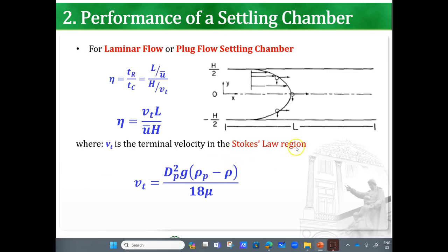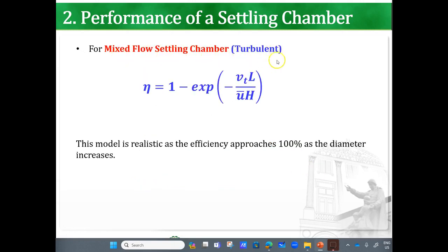Here v_t is the terminal velocity in the Stokes law region, given by: d_p² × g × (ρ_particle − ρ_fluid) divided by (18 × dynamic viscosity μ). For a mixed-flow settling chamber in the turbulent region, the efficiency is 1 minus e raised to the power of negative (v_t × L) divided by (u × h). This model is realistic as efficiency approaches 100% as particle diameter increases.